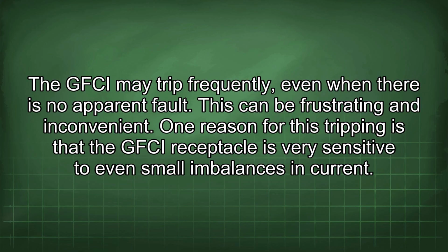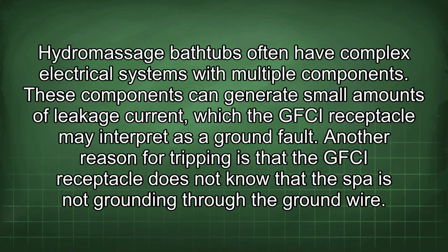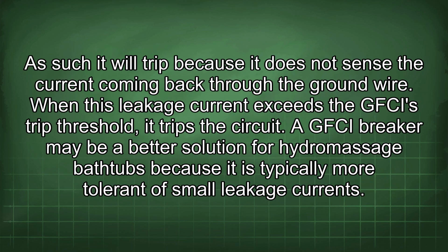One reason for this tripping is that the GFCI receptacle is very sensitive to even small imbalances in current. Hydromassage bathtubs often have complex electrical systems with multiple components. These components can generate small amounts of leakage current, which the GFCI receptacle may interpret as a ground fault. Another reason for tripping is that the GFCI receptacle does not know that the spa is not grounding through the ground wire. As such, it will trip because it does not sense the current coming back through the ground wire. When this leakage current exceeds the GFCI's trip threshold, it trips the circuit.